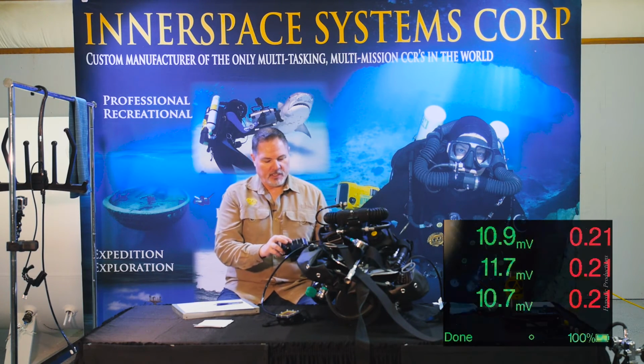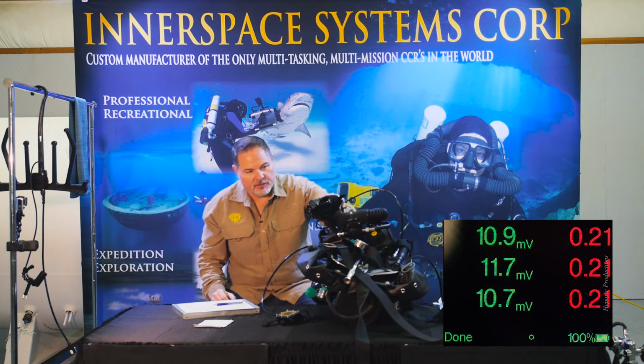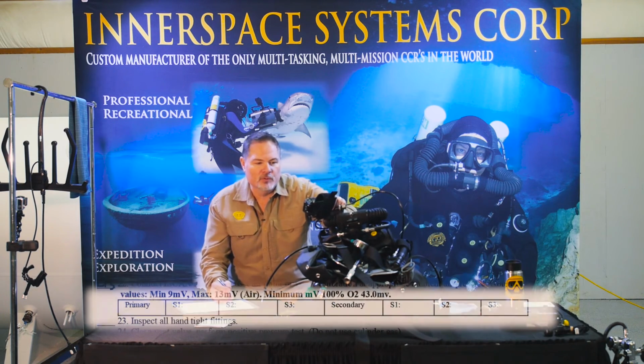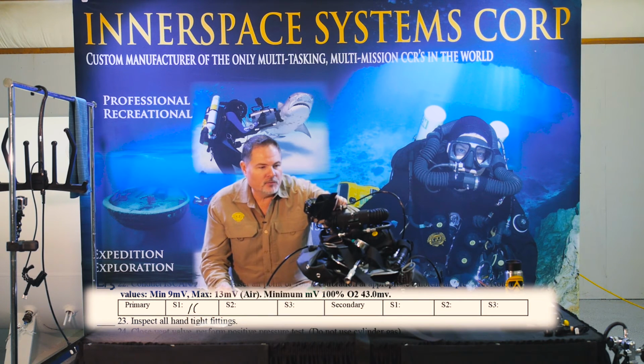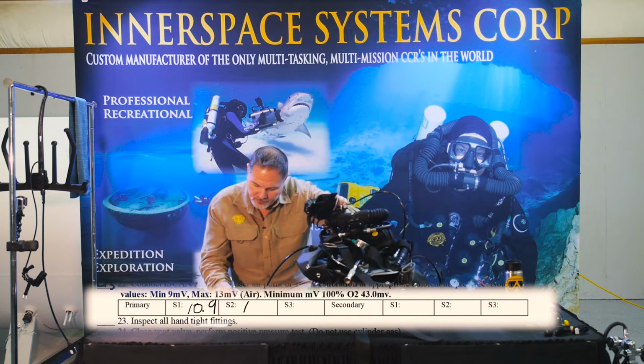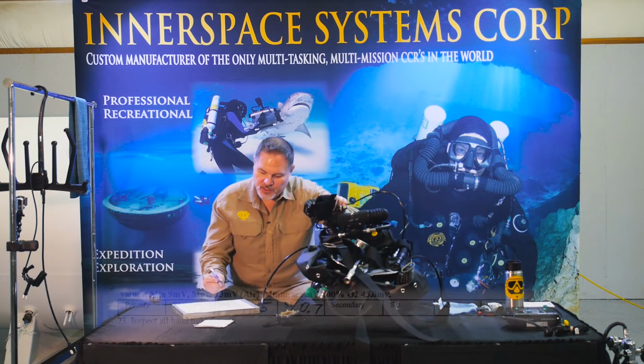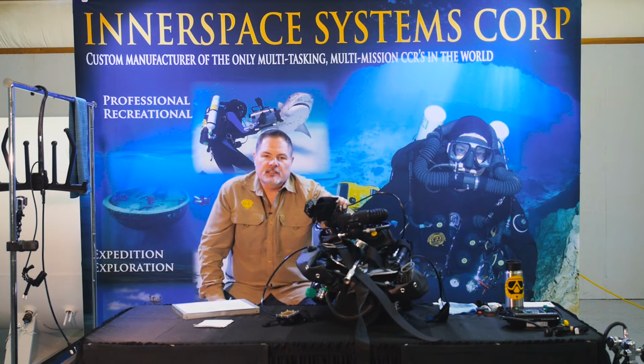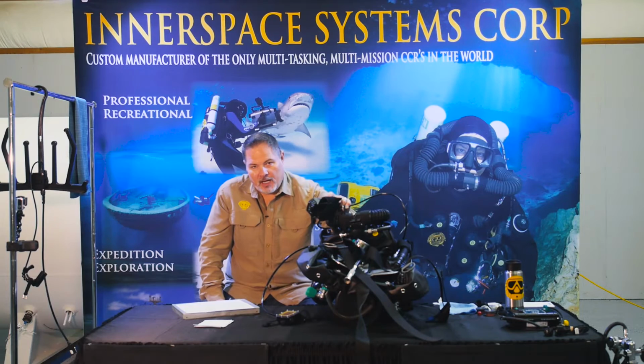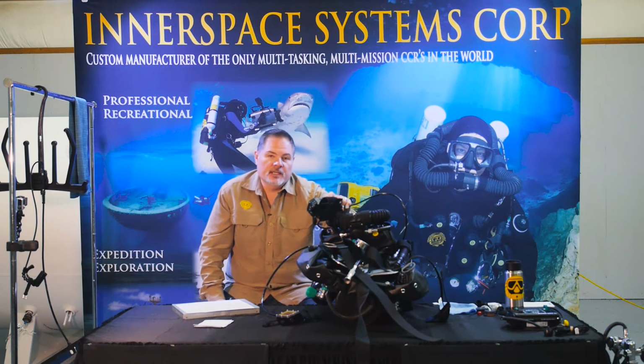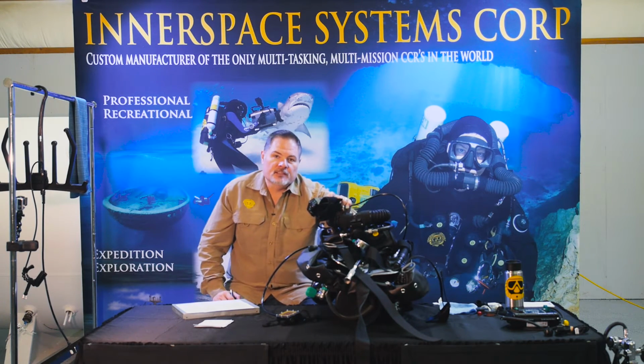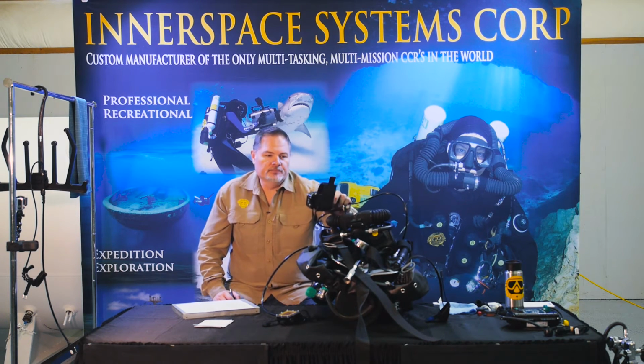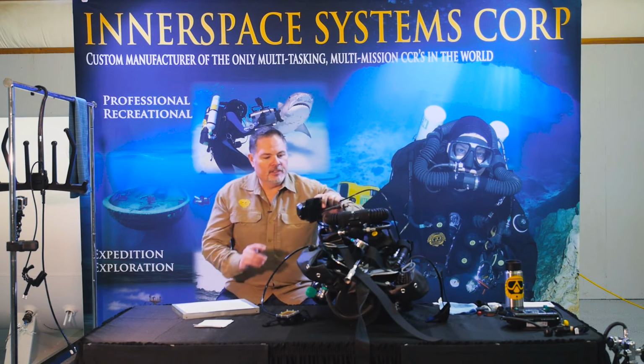And I'll go to the sensor menu, and I'll write down the millivolts on the sensors, and I'm reading 21 across the board. On sensor 1, I've got 10.9, 11.5, 10.7, all within the range. And the range for the ISC sensors is between 9 and 13 millivolts. And of course, this is at sea level, right? Not at altitude, not below sea level. This is at sea level. All right, so I'm good to go there.